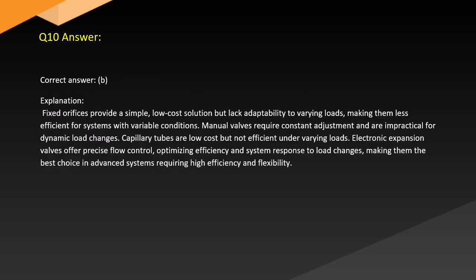Answer. Correct answer. B. Explanation. Fixed orifices provide a simple, low-cost solution but lack adaptability to varying loads, making them less efficient for systems with variable conditions. Manual valves require constant adjustment and are impractical for dynamic load changes. Capillary tubes are low-cost but not efficient under varying loads. Electronic expansion valves offer precise flow control, optimizing efficiency and system response to load changes, making them the best choice in advanced systems requiring high efficiency and flexibility.